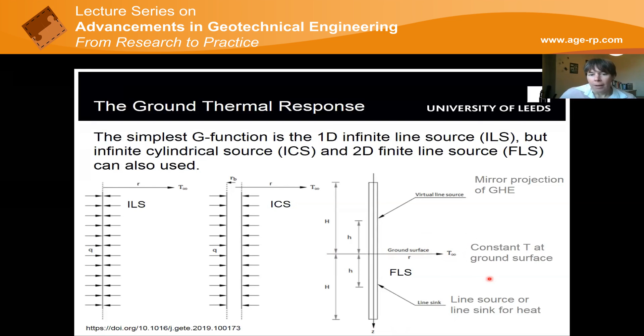An alternative is to assume our heat exchanger is still infinite in length but cylindrical in shape, with heating coming from the outside of that hollow cylinder, a model that's sometimes used. Finally, the most complicated of the three is the finite line source, where again we assume our pile is a line, but we take into account its finite length by having a line heat sink and a line heat source, and a mirror at the ground surface, which we assume is at constant temperature. All these solutions can be developed analytically.